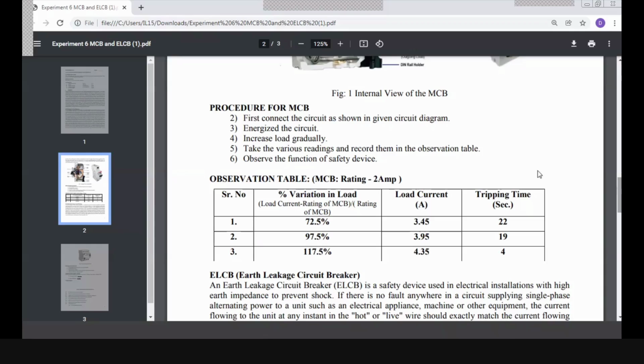You can see in the observation table this variation in load. We increased 72.5% of the load, then load current in the circuit was 3.45 ampere, which is beyond the 2 ampere MCB rating, and so it is a condition of overloading.